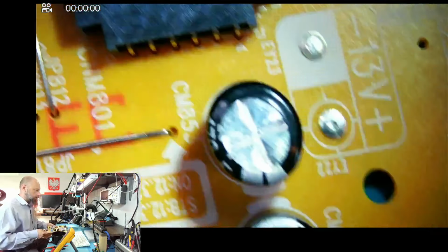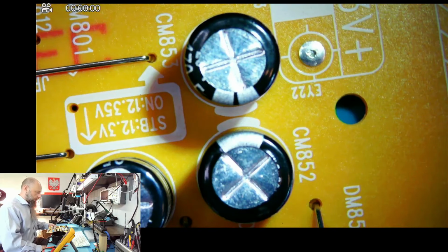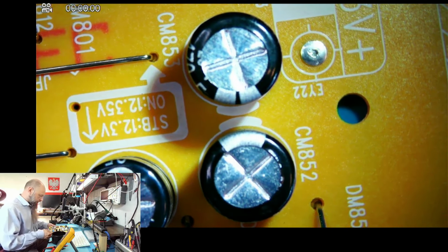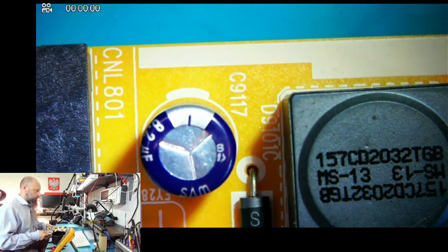If these all three are... well, they are, yeah, they're all three in parallel. So they're roughly 500 times 3, that's 1500, so that checks out. So our output capacitance is okay. Really no need to measure the ESR. I don't think the caps are at fault here. Neither the visual nor the measurements suggest that.